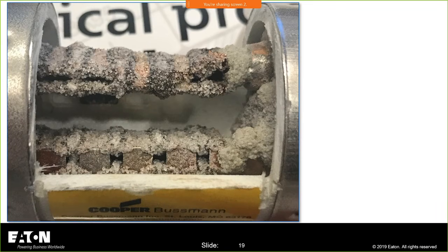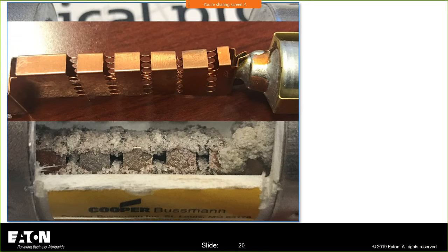And when one is actually done, this is a picture of a fuse. So you notice that the previous photo is pretty accurate in what this thing looks like. You see all of the pinch points were basically in here. These were that square element, right? And this is where that overload region is, right? We saw, and you'll notice there's two elements in here, not just one. And it's a dual element type of device. And these bear the brunt of the short circuit. And if I took one of those out and said, what does it look like brand new?